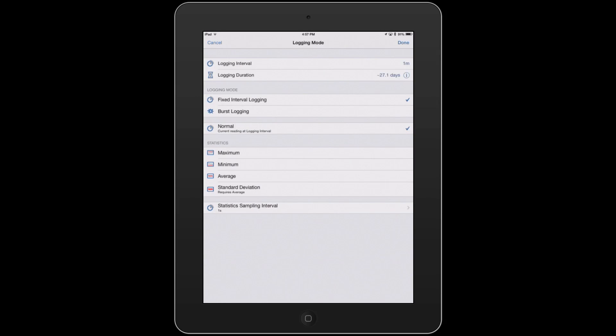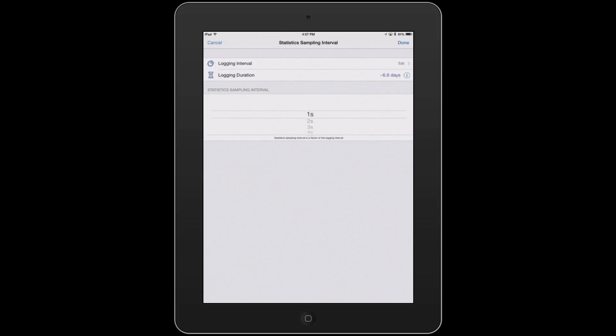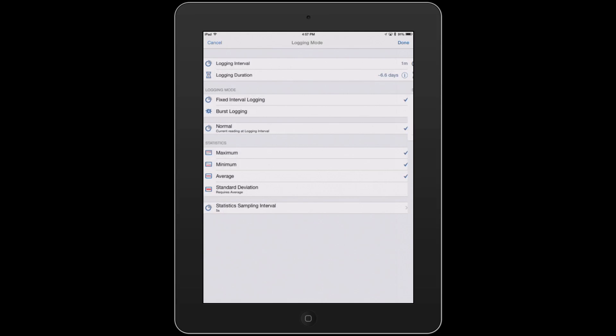So you can set it up at a fixed interval, so it wakes up every minute and takes a recording over that time frame. You could have it do statistics, so if you want to get the average, min, and max over that one minute interval, you could then have it take a sample every five seconds. Select Done.